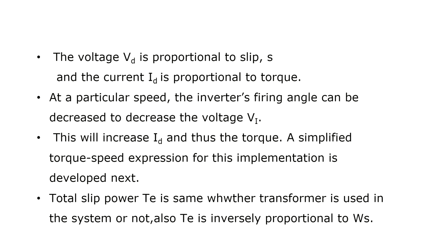From the analysis, we can conclude the voltage VD is proportional to slip S and the current ID is proportional to torque. At a particular speed, the inverter's firing angle can be decreased to decrease the voltage VI. This will increase ID and thus the torque. A simplified torque speed expression for this implementation is developed next. Total slip power TE is the same whether a transformer is used in the system or not. Also, T is inversely proportional to omega S.